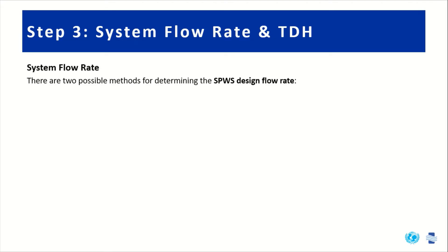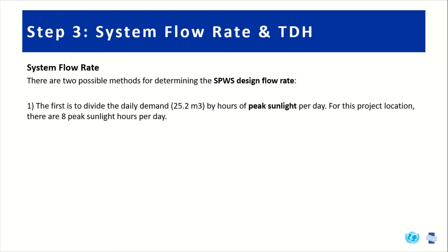We'll start with the system flow rate, and there are two possible methods for determining it. The first is to divide the daily demand — which was 25.2 cubic meters — by the expected hours of peak sunlight per day. For this project location, we estimate eight hours of peak sunlight per day, giving us 3.2 cubic meters per hour.